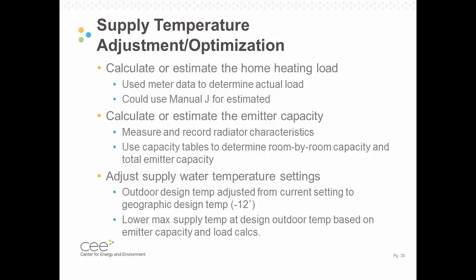So given that we know what we know about the house and doing those sort of estimates, we kind of walk through the adjustment. So we take that heating load that I mentioned we calculated for this house, we look at that emitter capacity, and then we modify that supply water temperature curve so that it gives us the minimum supply water temperature at the various outdoor air temperatures that will still meet the house's heating load.